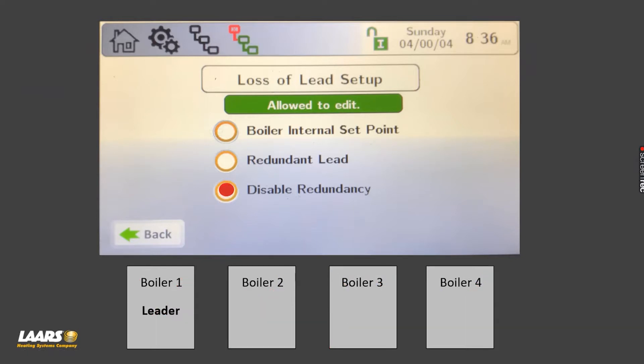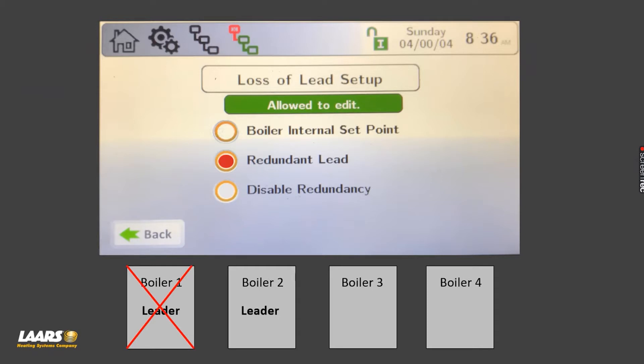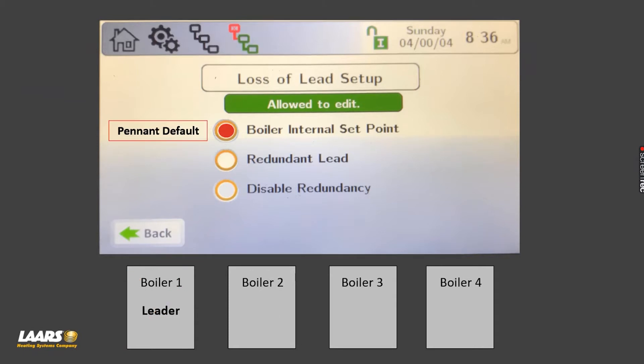Redundant lead: we can actually choose two leaders. Here I'm showing boiler one as a leader — we could also make boiler two as a leader. Boiler two in this example would also need a system sensor. If somebody had to power off one of the leaders for maintenance or service, your remaining leader would take over and operate the bank of boilers, giving you backup redundancy.